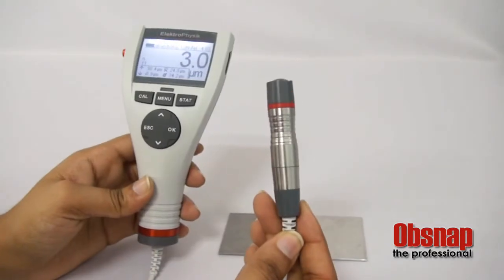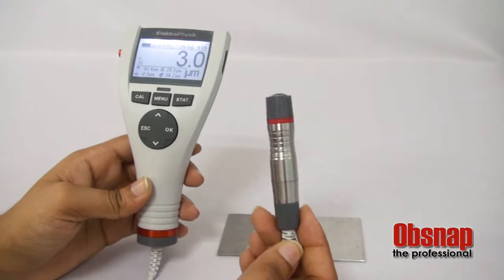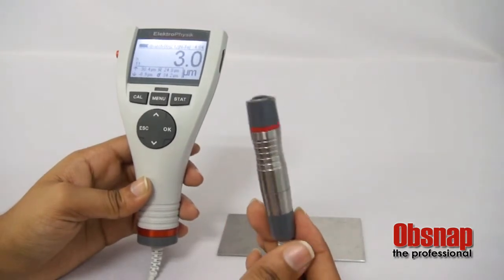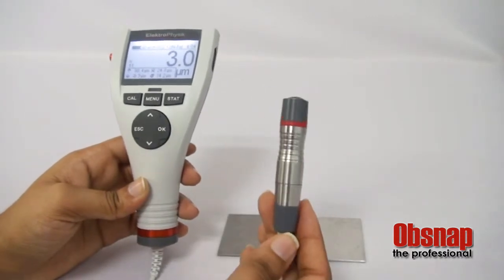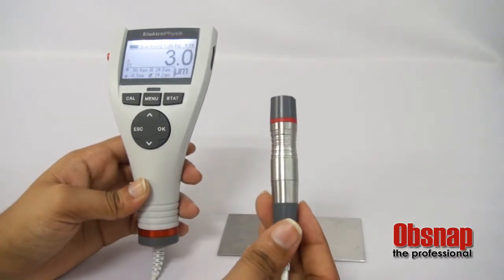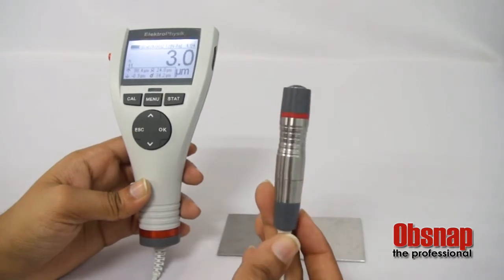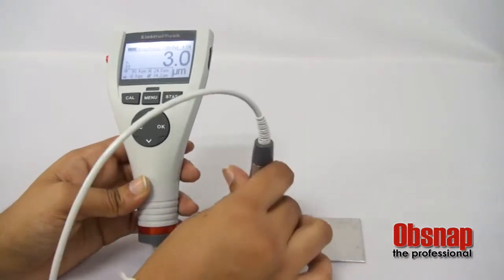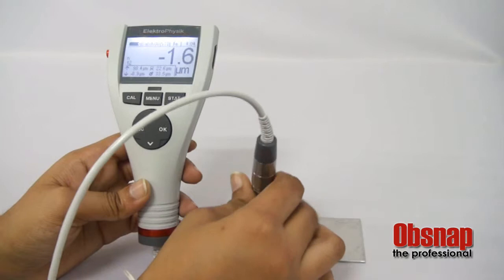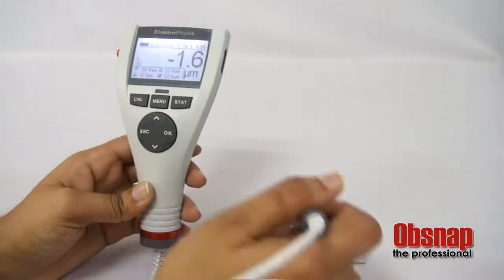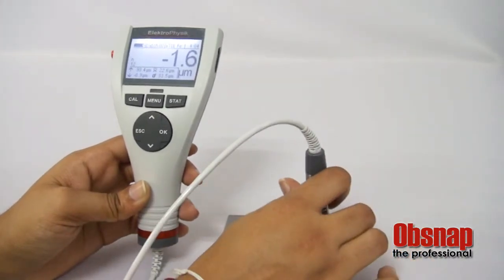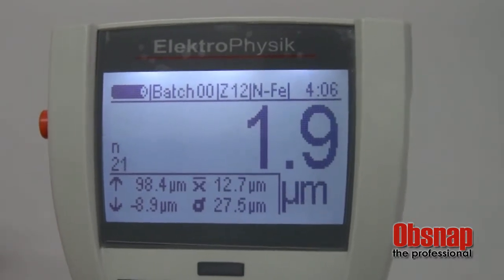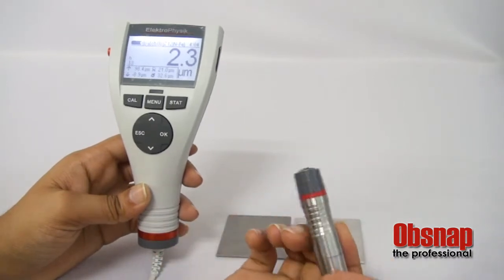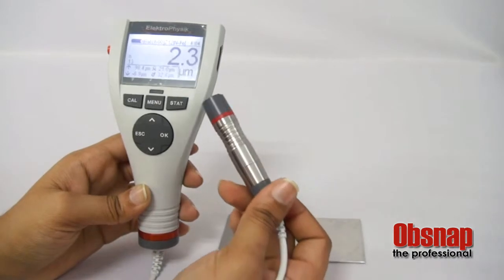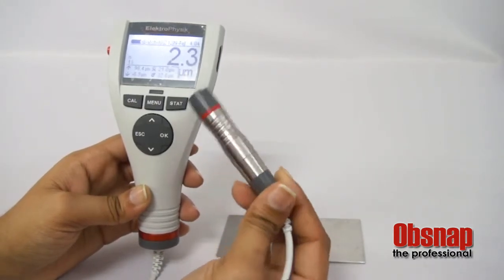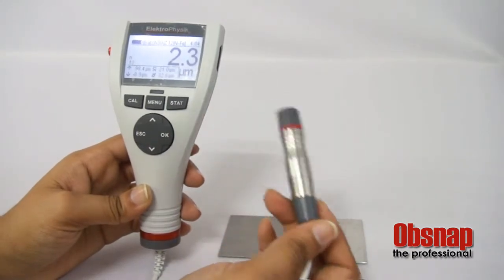This is the sensor probe, the external sensor probe. This external sensor probe has ferrous and non-ferrous, so we are able to do measurement for both. Ferrous uses magnetic induction to do measurement, whereas non-ferrous uses eddy current. So right now I'm going to do measurement on ferrous. When you do measurement on ferrous, the reading will display in ferrous, and you can even take the measurement on a non-ferrous plate, where the reading will be displayed in non-ferrous. So this gauge belongs to the FN sensor type. FN stands for ferrous and non-ferrous, which is able to measure in both.